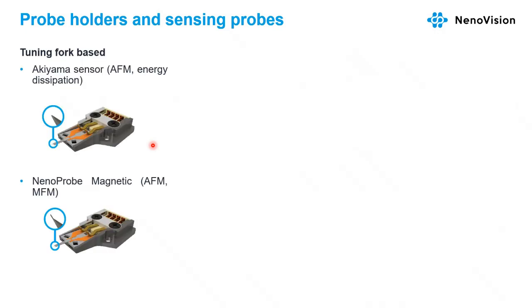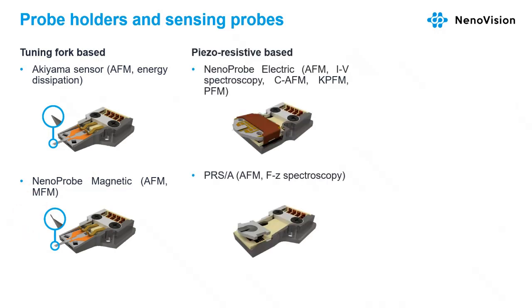For measuring the different properties, we need different probes and probe holders. We are using self-sensing probes. There are several types of them. One of them is tuning fork based, called the Akiyama sensor, which uses a tuning fork to oscillate with the cantilever, and it is for AFM and energy dissipation, or for magnetic measurements with a tiny magnetic tip. There are piezoresistive based probes, NenoProbe Electric, for several different measurements and modes, or piezoresistive self-sensing and actuating probes for force distance spectroscopy. And there are also other tips which can be used, for instance, for nanoindentation, the Berkovich tip.